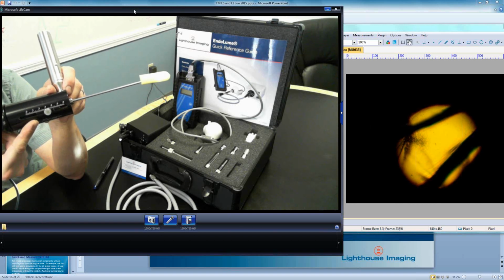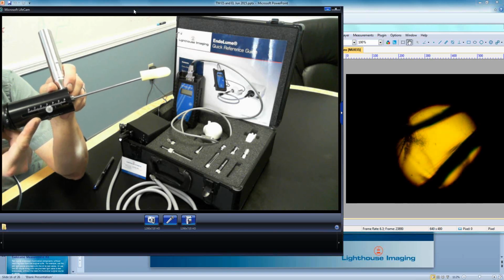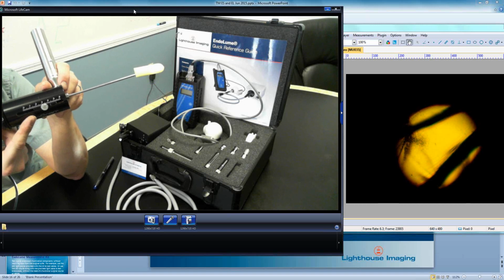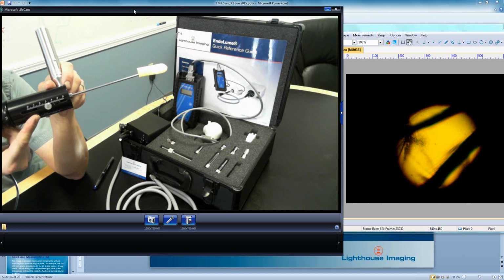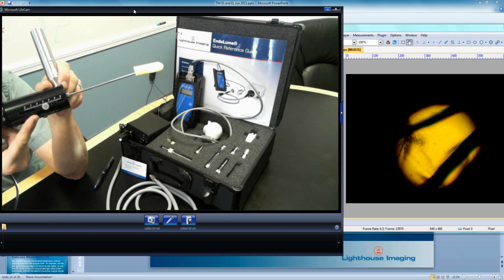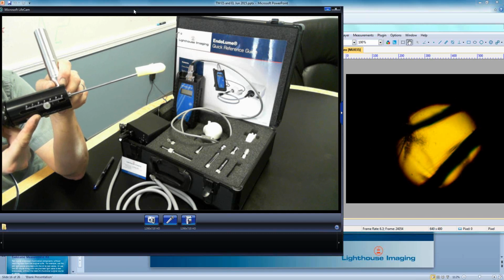If you had something more subtle, some debris, or probably most importantly some moisture leakage you could see—obviously if there's moisture leakage or any leakage, there's potential for contamination or cross-contamination. So that's something you might want to point out that's a little more subtle, like if you just saw a few droplets, which can be harder to point out and see.